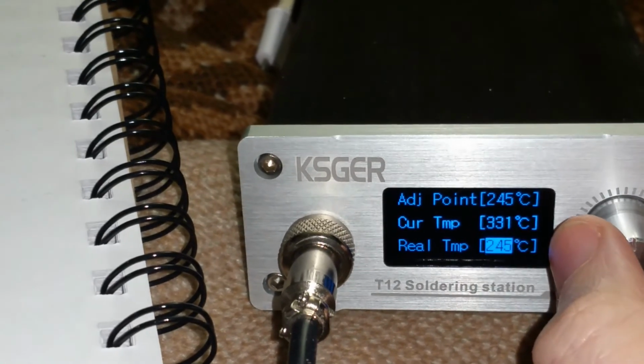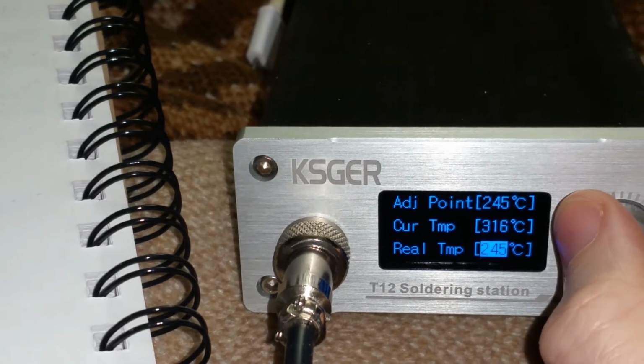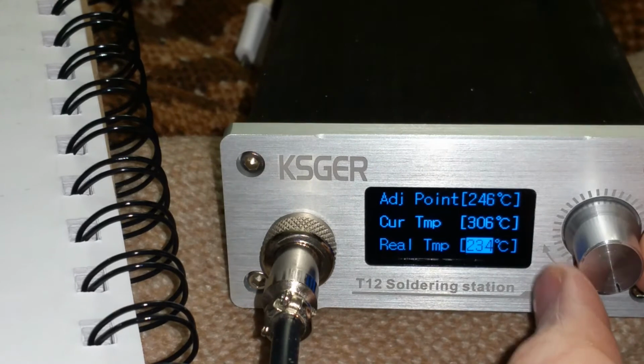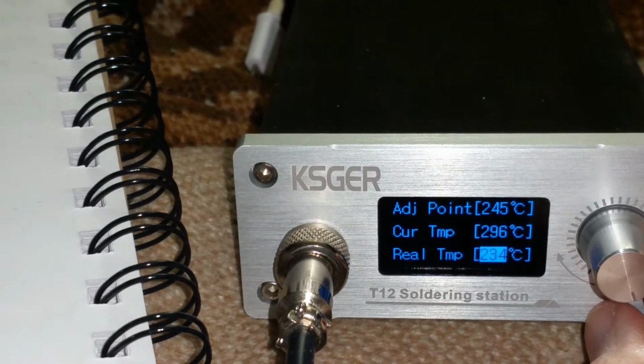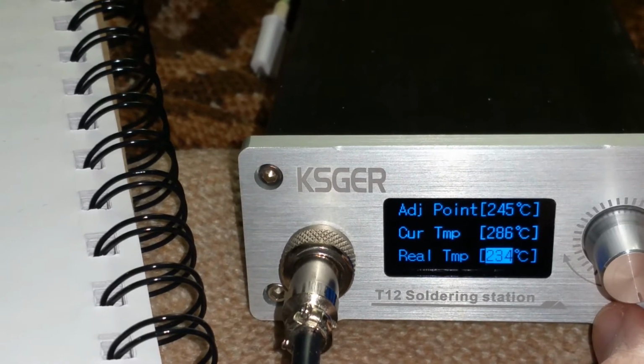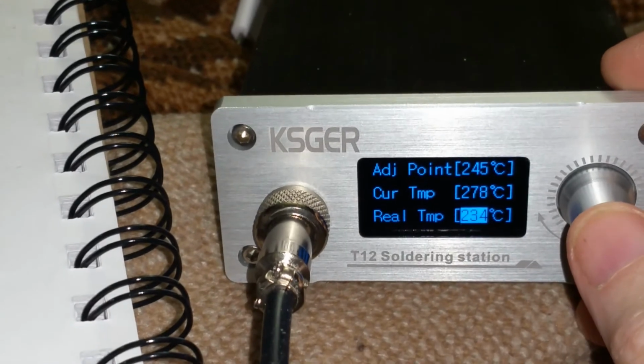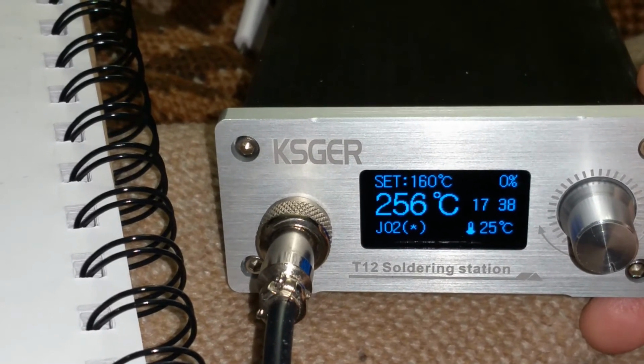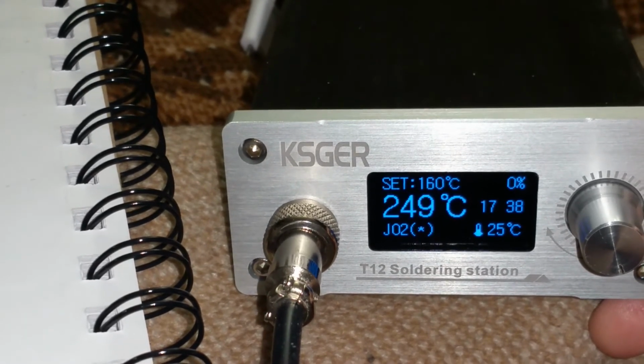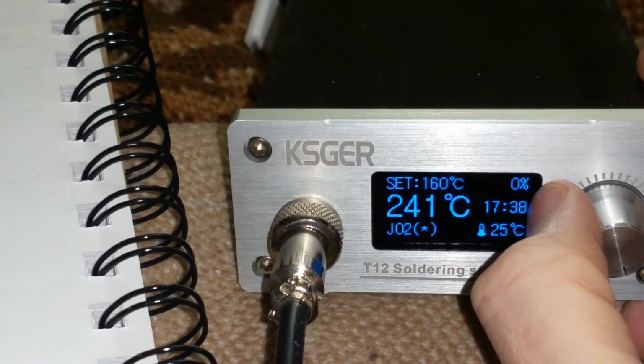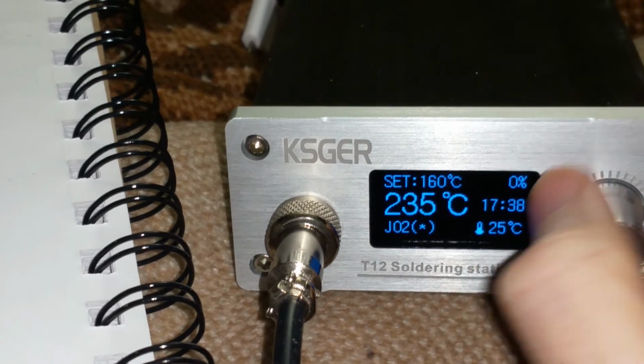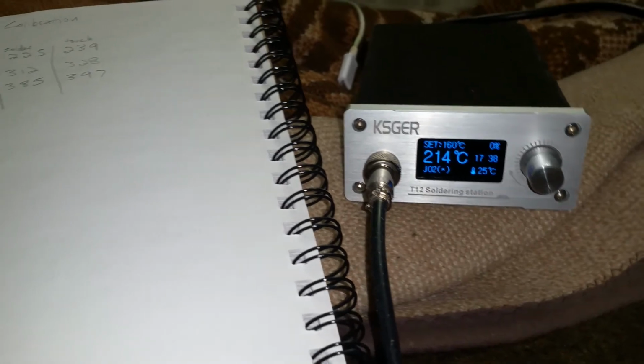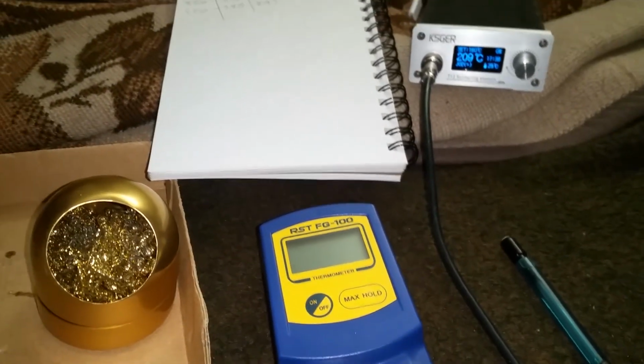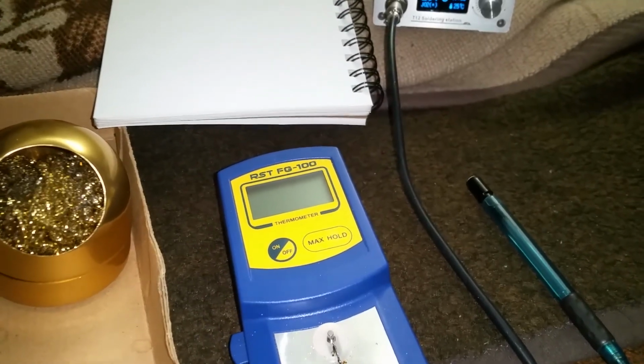Then 250, let's go down 11 degrees. So that should be our 3 calibration sensors. Okay, now it's going to go back. I noticed they showed the real-time temperature. I guess they want you to test it as you're going through this menu. I tested the 3 temperatures beforehand. Okay, and I'm going to test these 3 on my little meter here, and I will do a second video showing the results. Thanks.